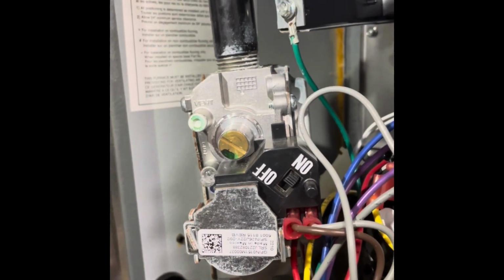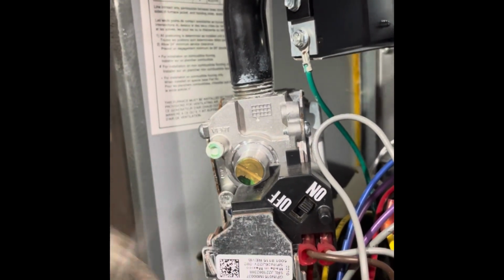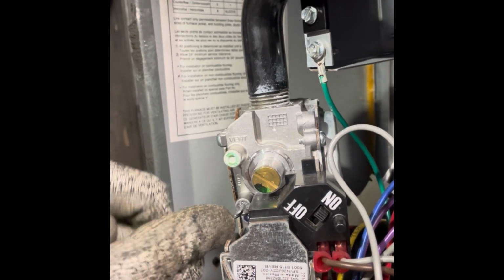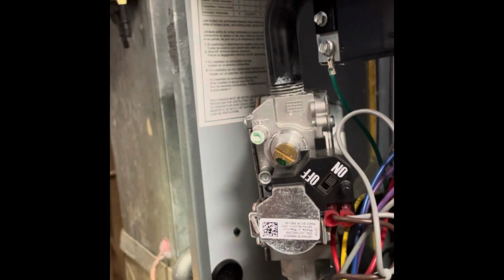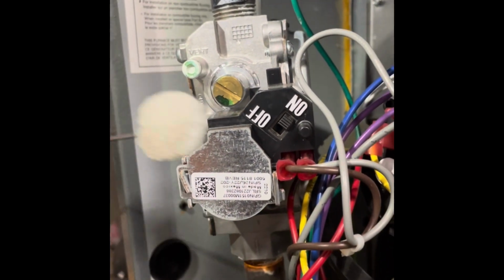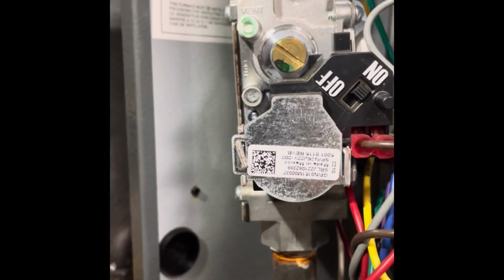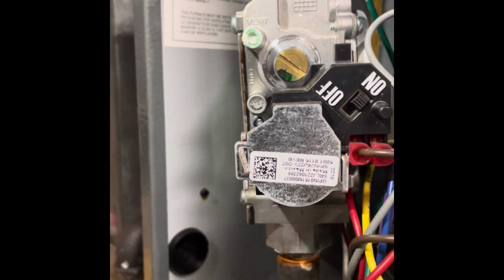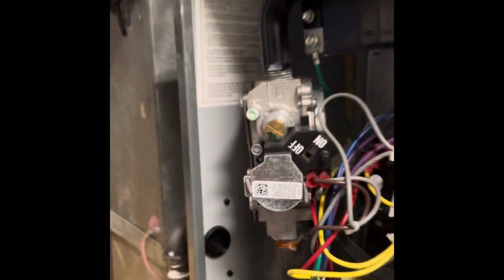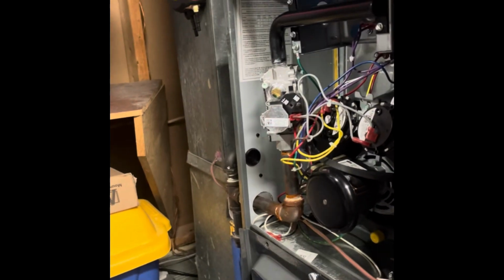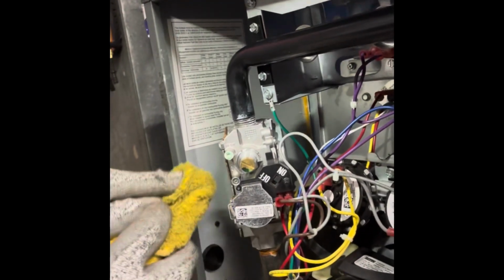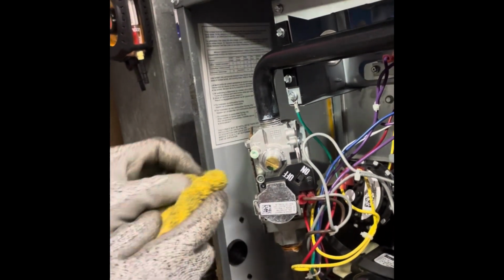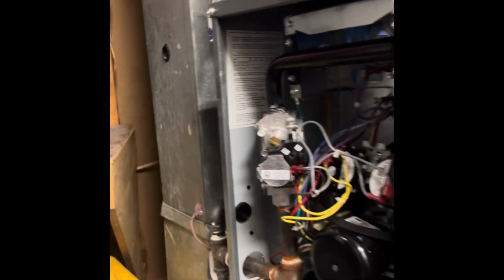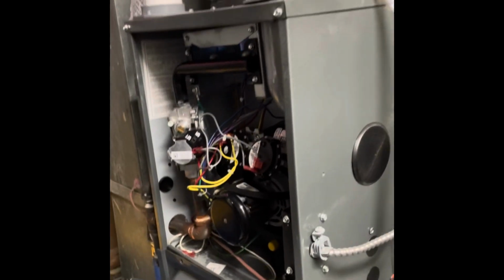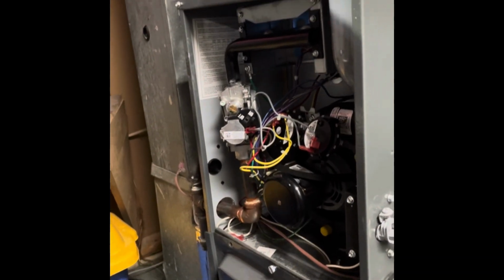So in order to stop that leak, I'm just going to turn to the right, make sure I tighten it. And what I'll do is I'll just apply a little bit more soap on there, just to make sure that it is not leaking. As you guys can see, we've got no bubbles. Those bubbles aren't blowing up anymore. That port's closed and no leaks. So last thing I want to do, again, we want to take that soap out of there, because we're going to get white stuff building around that little port, and that could cause a little leak in the future. So we'll just make sure none of that stuff's there. And then I'll wipe this door down, and we've just got to go upstairs and turn your heat down now.